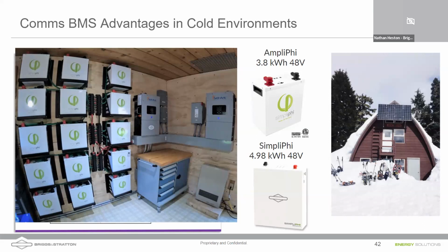So there are output ratings on the batteries. Batteries are designed for different discharge and charge rates. You would never take one of these 24-volt batteries and hook it to a 24-volt vehicle and charge and run it through the starters, right? If you did that, you would damage the battery. Car batteries are designed for really high cold cranking amps. These batteries are designed to last a long time and to output power for numbers of hours, but not designed for huge amounts of power.